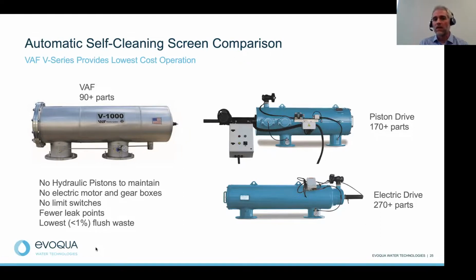10 to 15 seconds, and ultimately a cycle is completed, dropping that DP down again for filtrate, for again a full clean screen. And just one more note: when a cleaning cycle is active, the filtration is still functioning. You are not shutting this filter down when you are in cleaning mode. Something very important to be evaluating when you're choosing the right technology. And lastly, this type of technology provides the lowest flush waste in the industry, less than 1% of the overall feed flow.